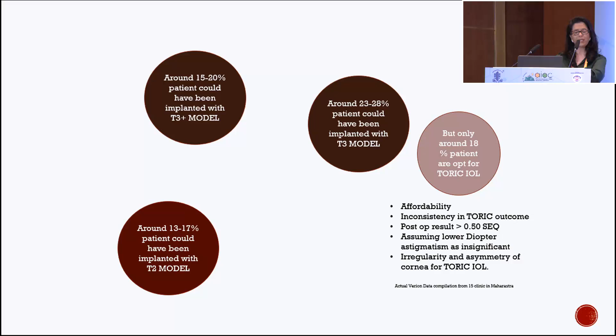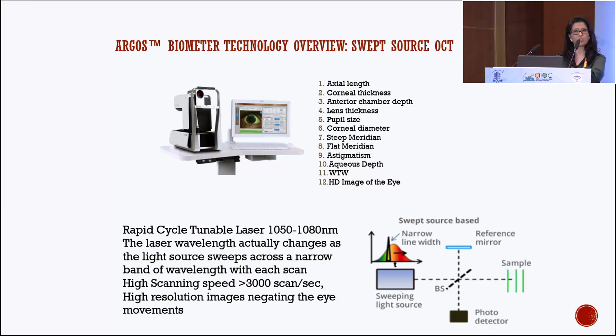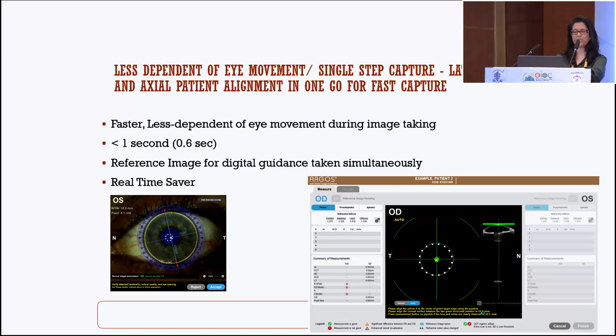So this is the idea that we go beyond biometry. We see what is available to us in the market and then improve our astigmatism and toric corrections. Here I'm talking about a newer generation biometer, the Argos from Alcon. It uses the SS-OCT swept-source technology. The beautiful part of this is that the acquisition is so fast that it is very less dependent on any kind of eye movement. So the learning curve for any optometrist becomes very less. It is highly precise because it takes a reference image for digital guidance, which takes measurements simultaneously from anterior to posterior and posterior to anterior, being a real time saver.